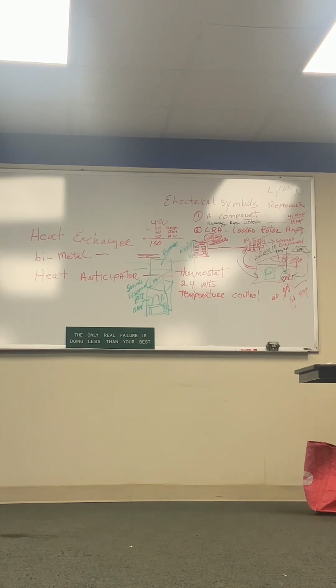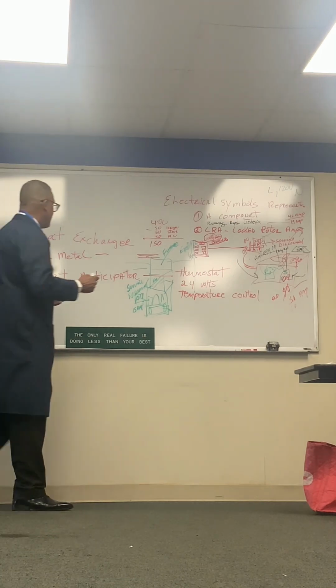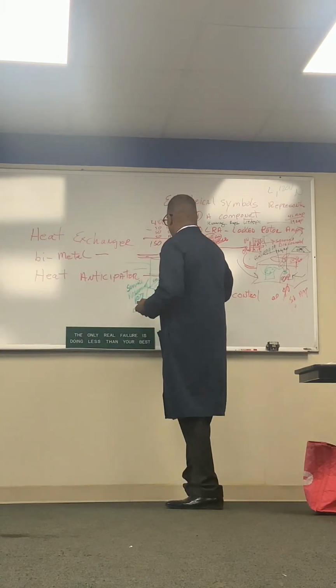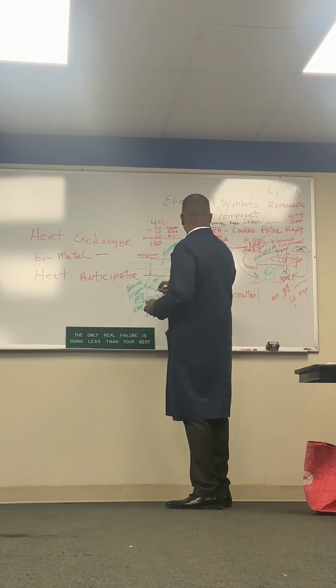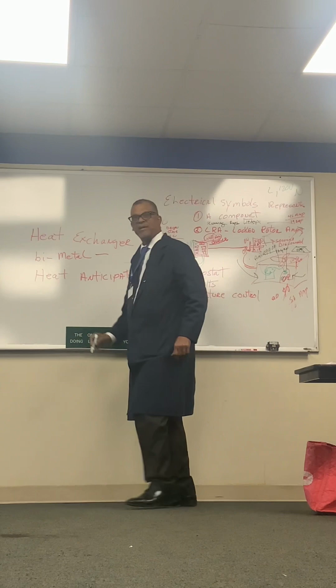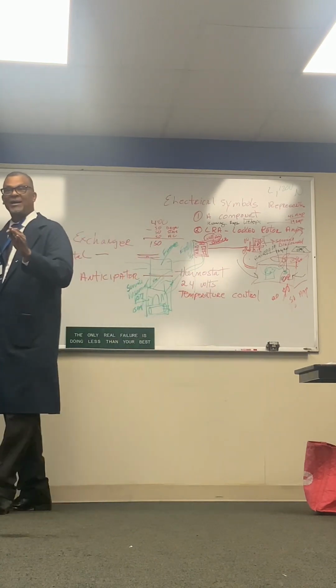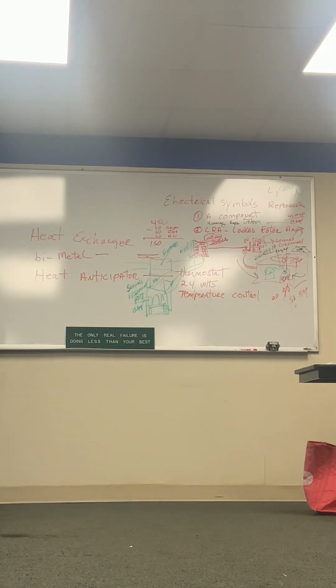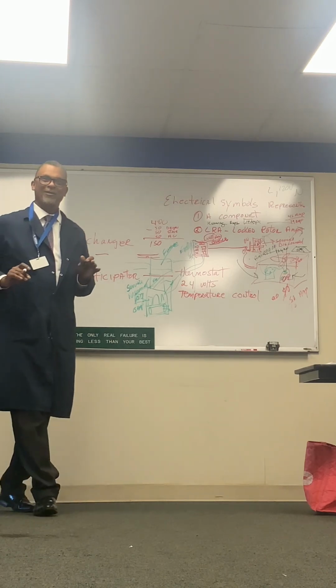So it would be a transformer somewhere to get the 120? How do you get the 120? The 120 doesn't come from a transformer. The 120 for this furnace, where we're bringing it in right here, comes from the breaker box. That's why we said it's a breaker box or load center, which means it carries the load for each device with a coil.